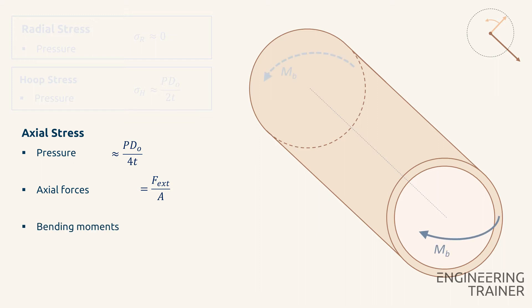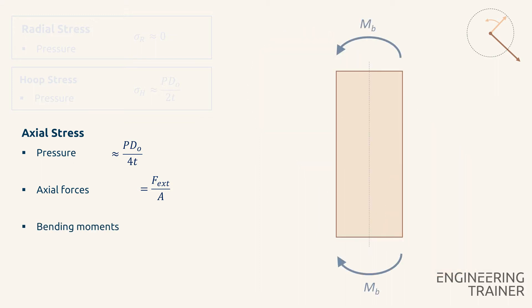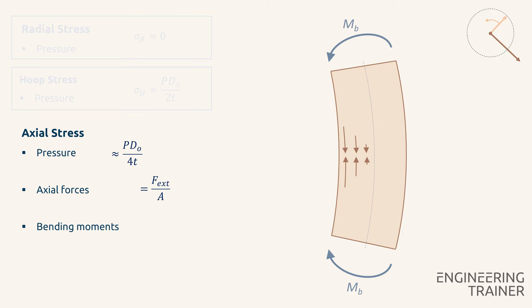Additionally, bending moments can cause axial stresses. If we consider a top view of a pipe piece to which a bending moment is applied, we find compressive stresses on one side and tension stresses on the other side. On the compressive side the stresses are negative and on the tension side the stresses are positive, similar to a beam under bending.